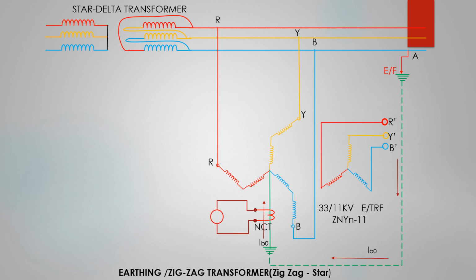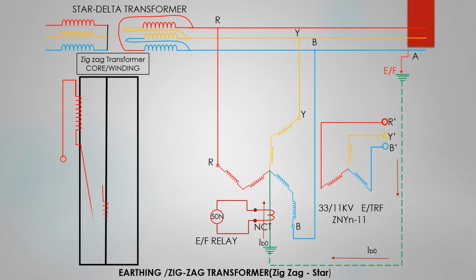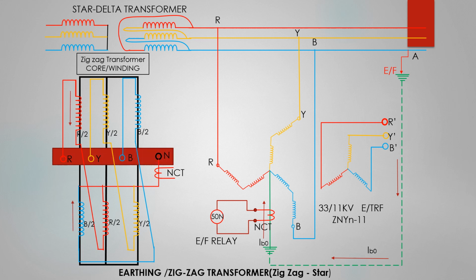So, during an earth fault, relaying is done through an earth fault relay, which is connected with the NCT secondary. Each phase of the primary has two equal parts. The three windings each have two parts providing opposite flux during normal condition. Since the fluxes are opposite, the transformer takes only a little magnetizing current during normal operation.